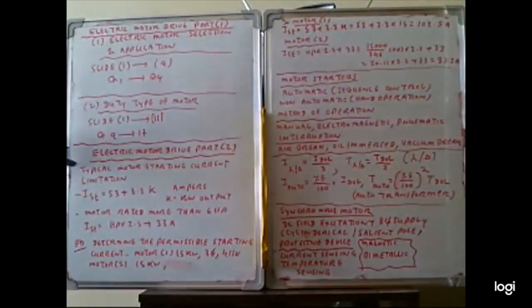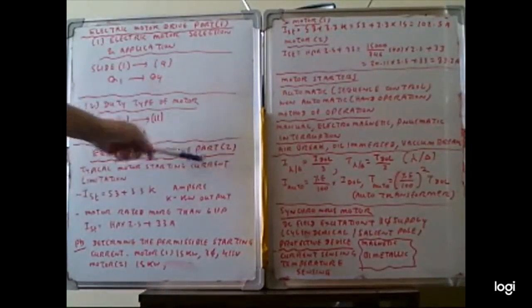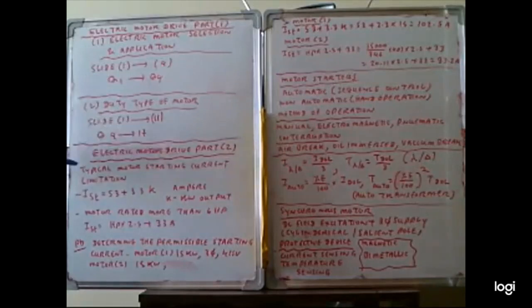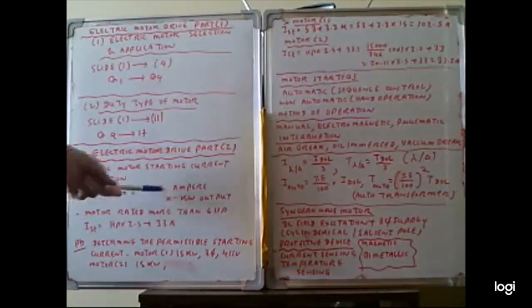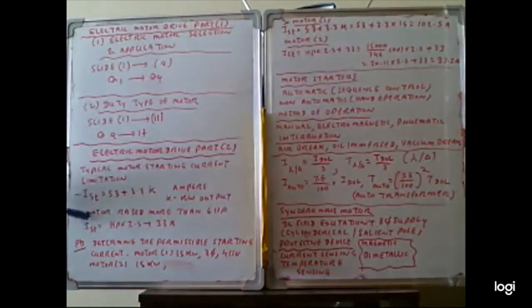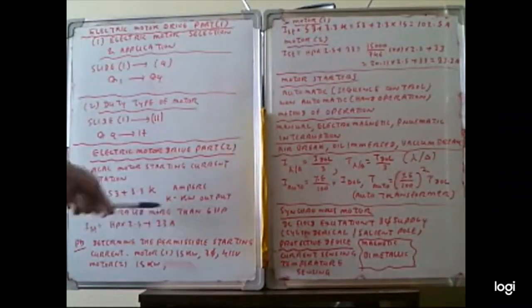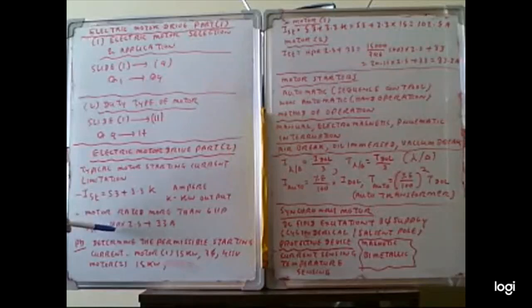When you connect the electric supply to a three-phase induction motor, the motor draws a higher current at the starting time, so the starting current needs to be limited. A typical formula is I_ST equal to 53 plus 3.3 K, where 53 and 3.3 are constants and K is the kilowatt output. For motors rated more than 6 horsepower, the starting current must follow this formula: I_ST is equal to HP multiplied by 2.5 plus 33 amperes.